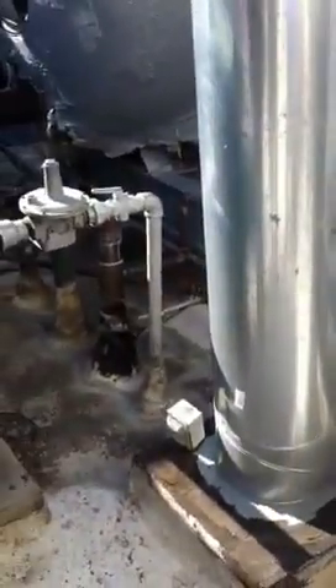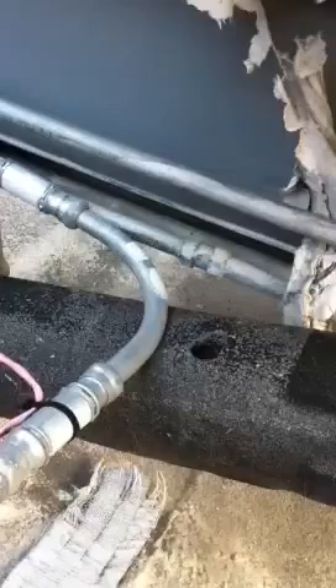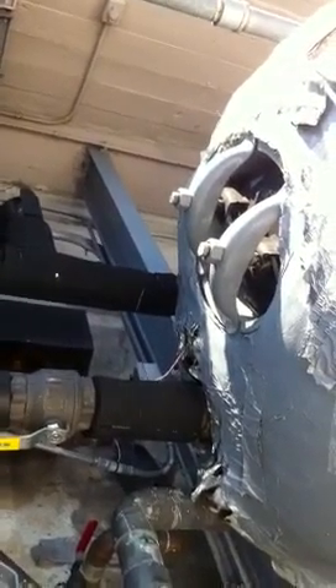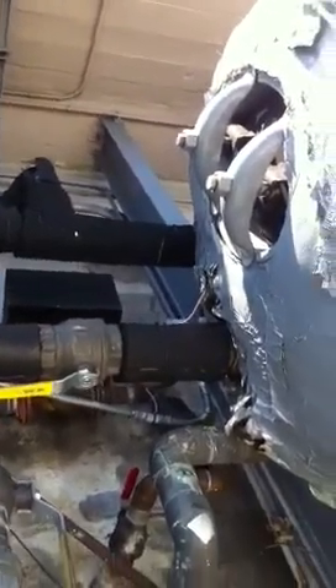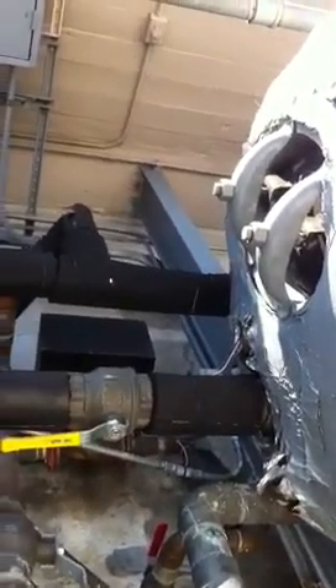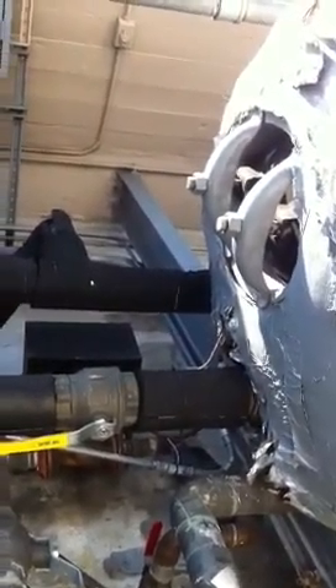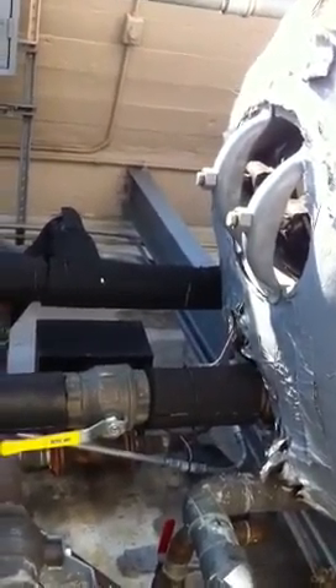All right, it's going to be hard to see, but that pump underneath the cover over there on the ground, piping. The piping on the outlet side of the pump, which connects to the boiler side, not the piping coming out of the roof, that's going to remain, but it has to connect into what we call the outlet pipe of the boiler, so it goes into the tank. So it circulates and picks up the hot water from the storage tank and circulates it through the building piping.